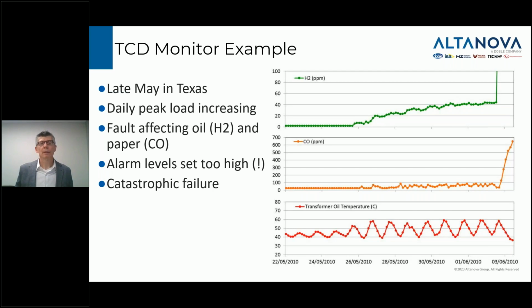Unfortunately, the user of this monitor did not set their automatic gas alarm levels at the optimal place. I think they had actually left the factory default settings, which were in the hundreds of ppm. So the main first lesson of this whole presentation today is, in order to ensure a good return on investment of a monitoring program, it's really important to set the gas alarm levels in the monitor based on the history of readings on that specific transformer. I'll maybe come back to that point again later on.